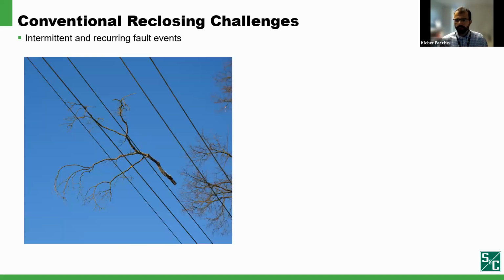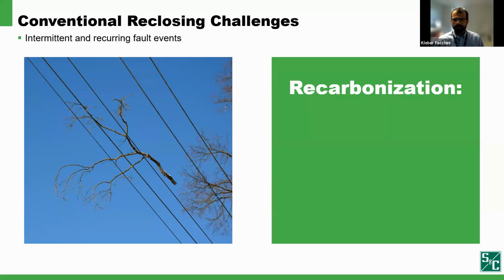Another issue all fault interrupting devices must contend with are faults that take time to redevelop when reclosing is practiced, usually due to recarbonization. Some faults redevelop or recur because their conductive fault path takes time to redevelop after being re-energized. This is what is called recarbonization. This typically happens after fault interrupters using conventional protection practices de-energize the fault path by tripping. They then reclose, re-energizing the fault path, which takes time to become conductive, and subsequently the fault reinitiates.